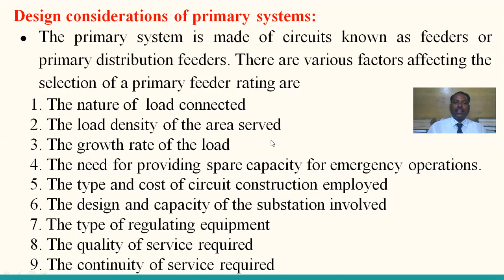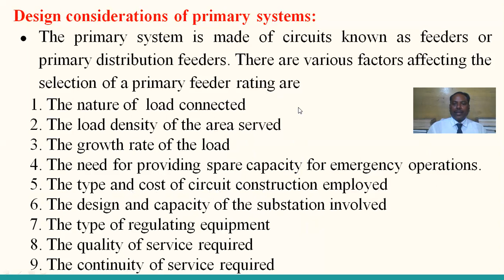See here clearly, very clear. There are various factors affecting the selection of primary feeder rating. Primary feeder generally carries 11 kV as well as 33 kV based upon the load density. So the primary feeder rating is decided by the parameters: nature of load connected, density of the area served, the growth rate of the load, spare capacity, type and cost of circuit construction employed, design and capacity of substation involved, type of regulating equipment, the quality as well as continuity of the service required. These are the major parameters which influence the primary feeder rating.